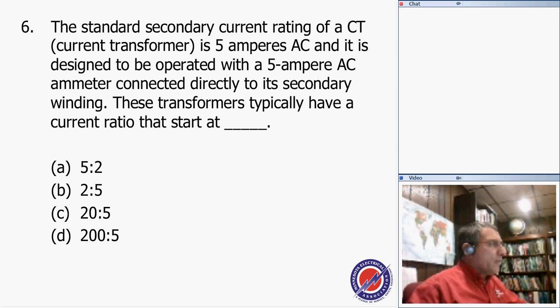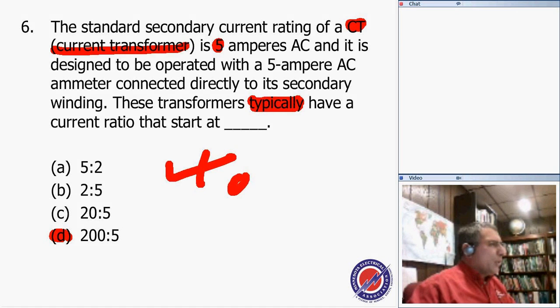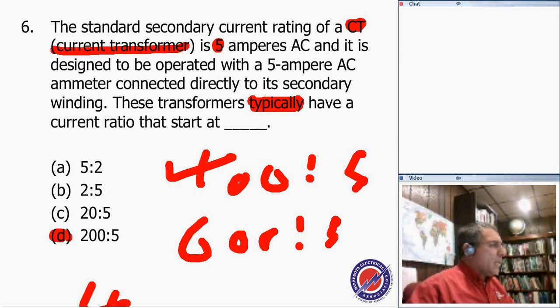The standard secondary current rating of a CT, a current transformer. This is really interesting, guys. The CT is always a current transformer in AC, and it's designed to operate with a 5 amp AC ammeter connected directly to the secondary winding. These transformers typically have a current ratio, number 6, such as 200 to 5. I emphasize the word typically, guys. In the industry, besides 200 to 5, you can have 400 to 5, 600 to 5, and you can go as high as 4,000 amps to 5 amps.